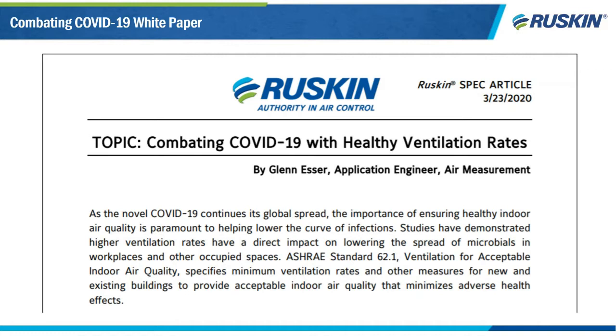ASHRAE standard 62.1 is the basis for minimum outside air requirements in the international building codes, and is most likely your local building codes as well. It shows the amount of outside air necessary to prevent your building from getting sick. No outside air is required in an unoccupied building. However, when even one person is in the building, then the building area component of the outside air is required.